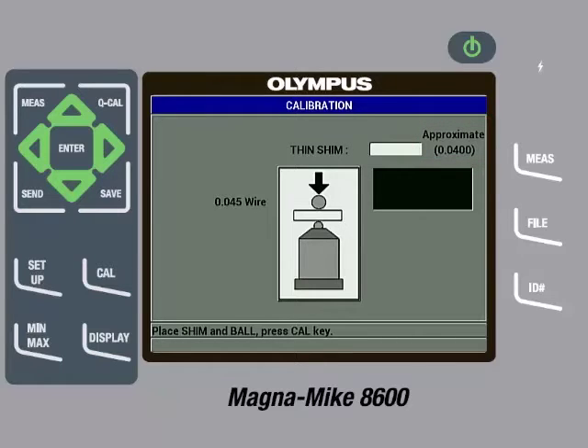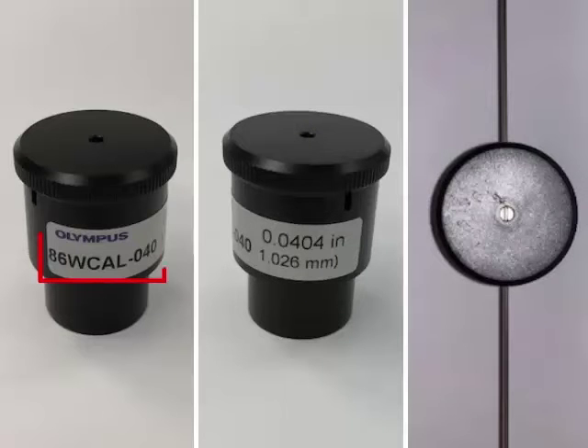The English units of approximate thickness being called out for the thin shim corresponds to a part number in the calibration kit. So the next step is to find the 86WCAL-040 reference standard. The reference standards include a shim made either of brass or aluminum that is a particular thickness. The actual thickness of the shim is printed on the reference standard in English and metric units. It is very important to enter the actual thickness of the shim and not the approximate thickness that is being called out by the instrument. In this case, the thickness printed is 0.0404 inches or 1.026 millimeters.